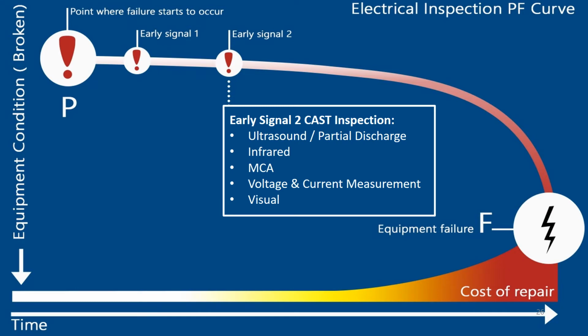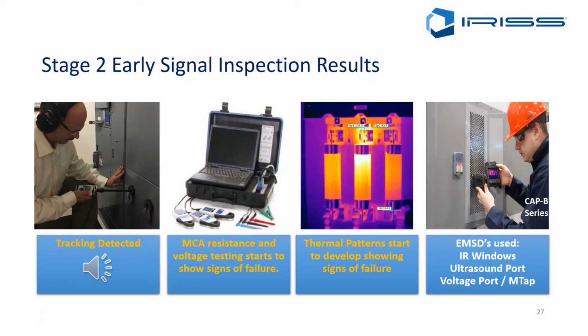Now, if we allow this to go further, we'll get to what we class as early signal 2. Again, we're utilizing the same equipment, but the results will start to escalate. At this stage, we're possibly going to pick up tracking. Tracking, unlike corona, is not voltage related, so we'll find tracking in low, medium and high voltages, and really this underpins the benefits of using ultrasound testing and partial discharge testing when we're looking at electrical equipment. Now, tracking sounds like this. Quite distinctive and very easy to pick out.